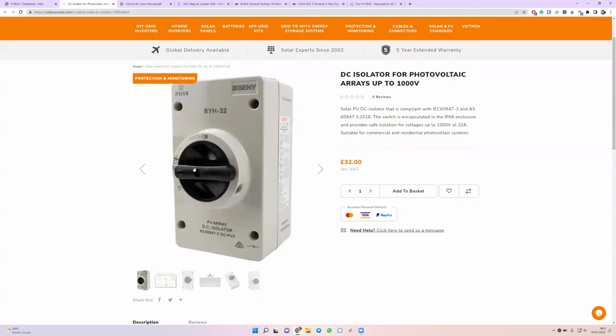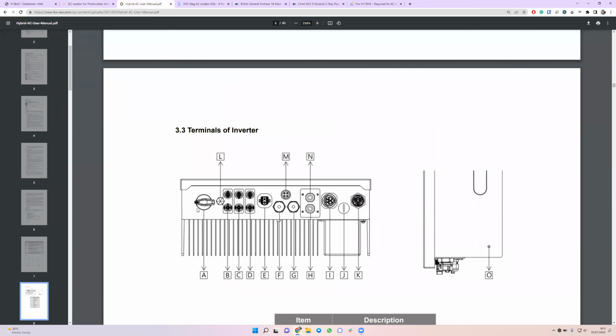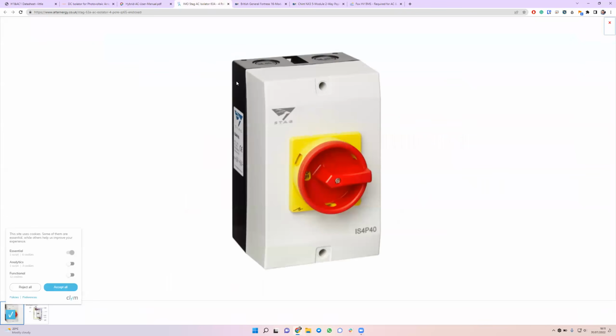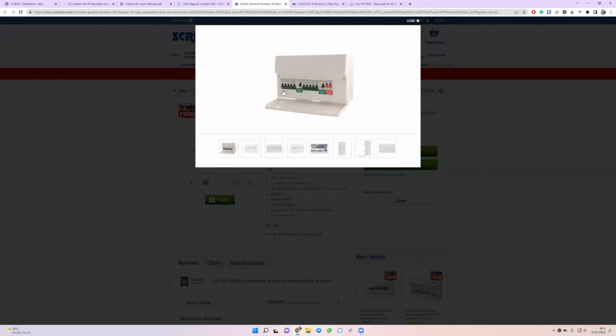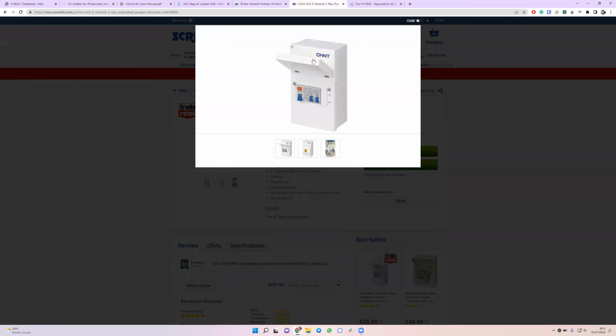We've isolated DC either via the DC isolator or via the switch on the bottom of the inverter. We've isolated the AC either by turning the AC off or breaking the circuit breaker that you have in your fuse box or in a box inside the meter box. You'll notice that the screen of your inverter is probably still on. Well, how can that be? I've turned the AC off, I turned the DC off. What else is powering this?